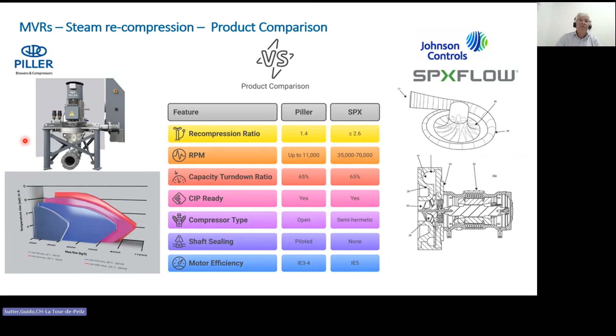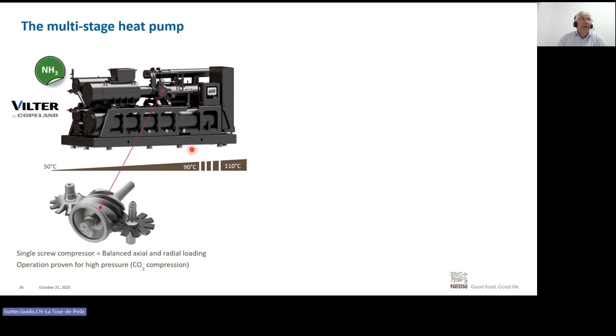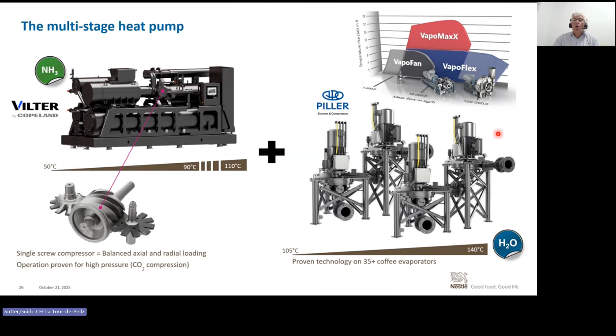What we also plan to do is to stretch the temperature of ammonia screw compressors from 90 degrees to about 110 degrees. We are working with a company, Vilter Copeland, with another type of screw compressors, which allows us to stretch ammonia to around 110 degrees. We are reaching system pressures of 80 bar instead of 50 bar at 90 degrees. And then from there, we would combine it either with, say, in this example here, 4-stage fans at 140 degrees, or eventually replace the fans with turbo compressors.